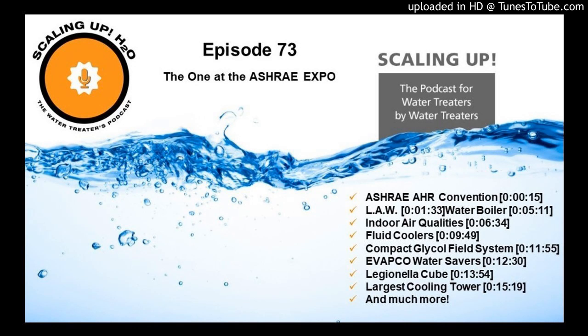And with the fin tubes, it can transfer approximately 30% more heat in the same size box. Somewhere it's 20 degrees higher in ambient temperature where you can flip it to dry, where it runs in all dry mode. So these aren't exact numbers, but say the one's capable of 35 degrees. This would be capable of maybe 55, 57 degrees. So anytime you're below that temperature, you can shut off the water and just run your process through the coil and cool it in dry mode.